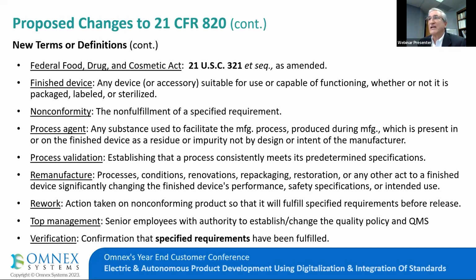You need to be careful recognizing that any imports coming into the U.S., it is good to make sure the device listing is included in the packaging or the packing list of those shipping documents. If not, they will be quarantined as possible use or as a finished device.